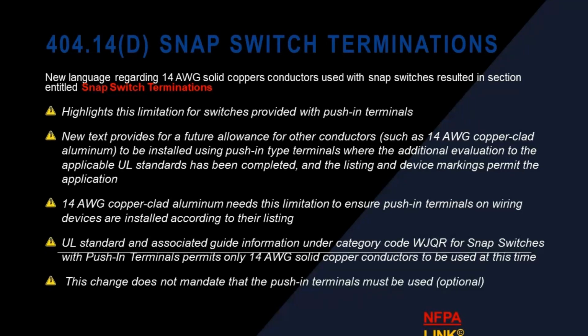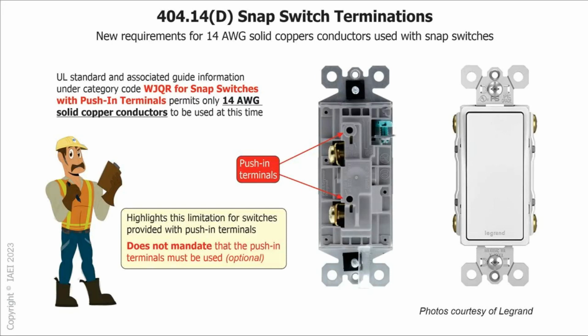Snap switch terminations. There's some new language in the 23 code. Solid copper conductors used with snap switches resulted in a section entitled Snap Switch Terminations. It highlights the limitation for switches to provide push-in terminals. So we're back to this 14 gauge thing. Like I said, you're going to see this because we are now allowing 10 amp circuits. They're going to start coming down on these devices a little bit more. Here's the push-in terminals of the switch, just like the receptacles we saw earlier.